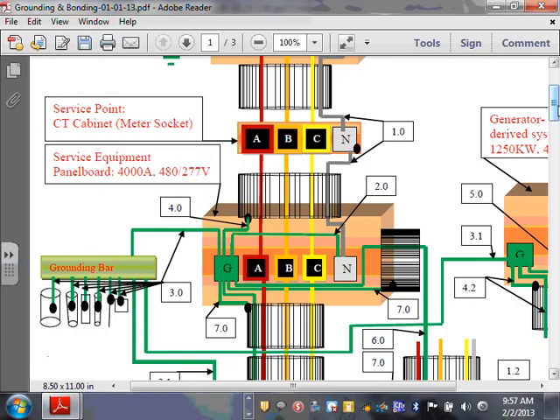We enter the building. When you enter the building, these are conduits. Let's say you enter with a rigid metal conduit. I brought corrosion-treated rigid metal conduit between my CT cabinet that I control into my building. Cool? You can bring PVC Schedule 80, right? Typically PVC Schedule 80 or rigid metal conduit inside.